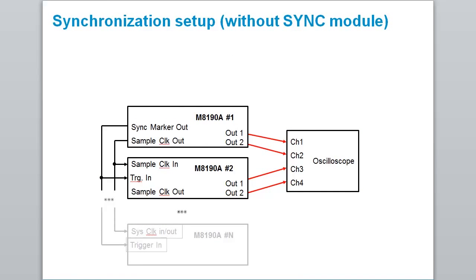But even without the synchronization module, it is possible to synchronize multiple M8190 modules by connecting the sync marker output of the first module with the trigger inputs of the other modules.